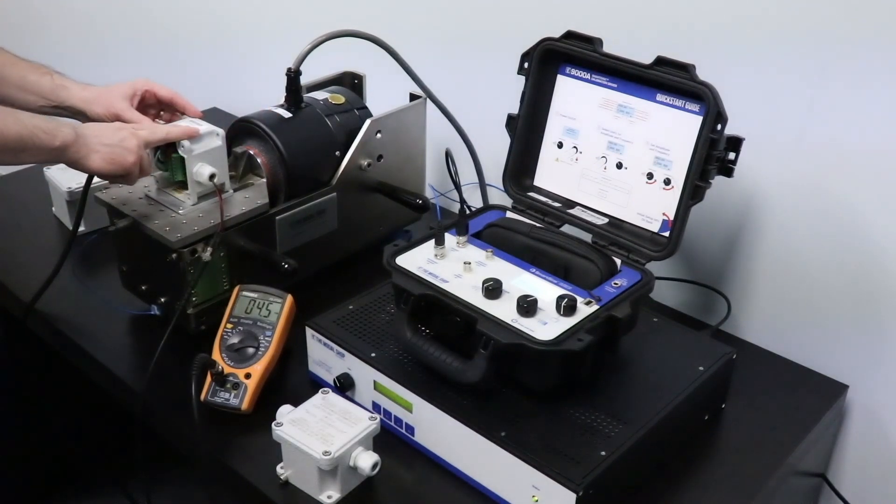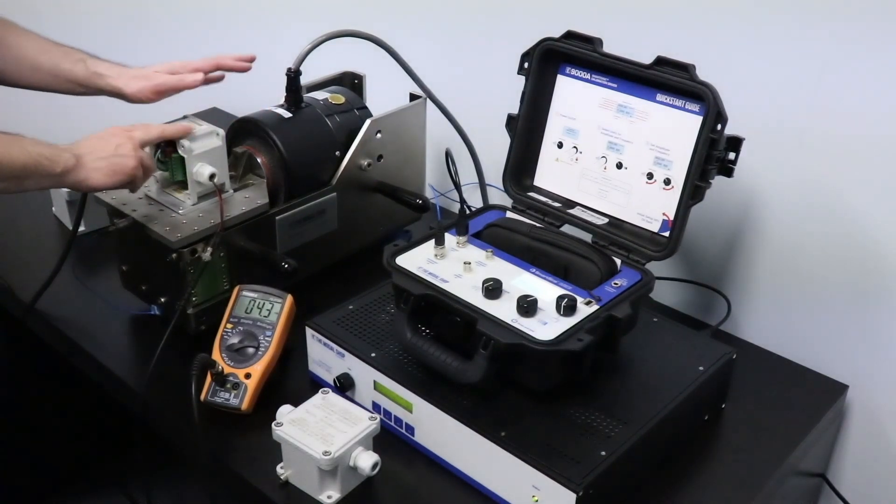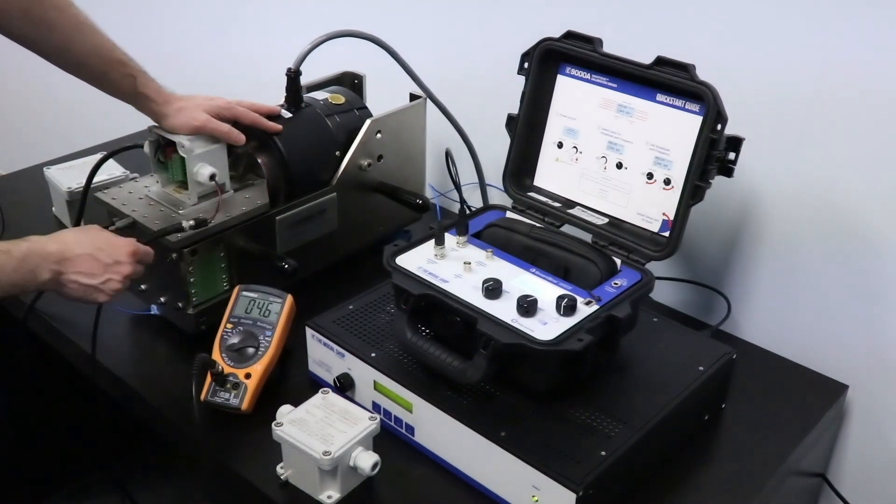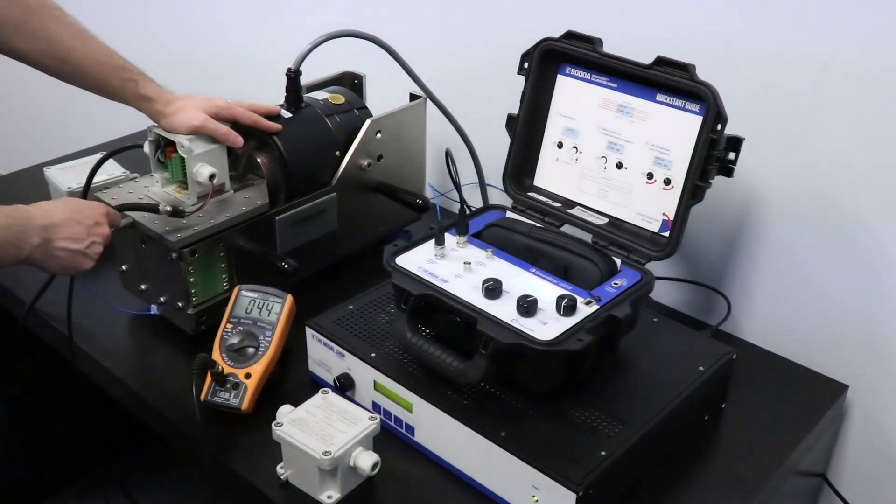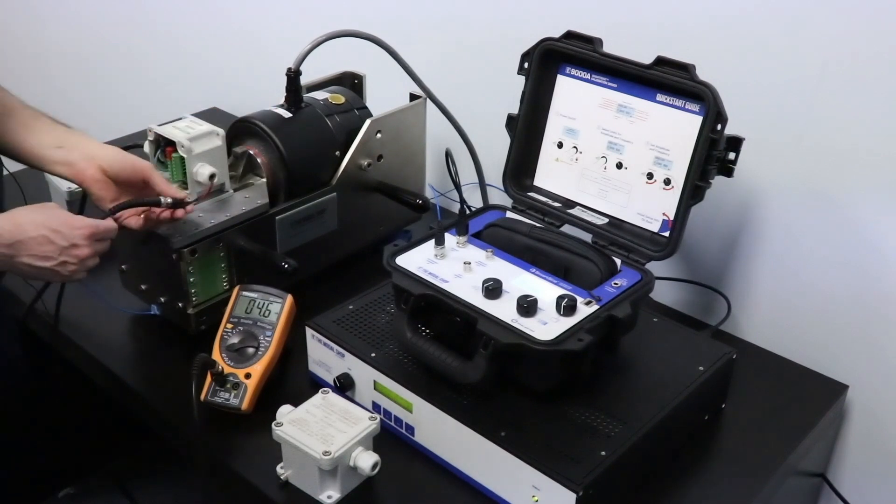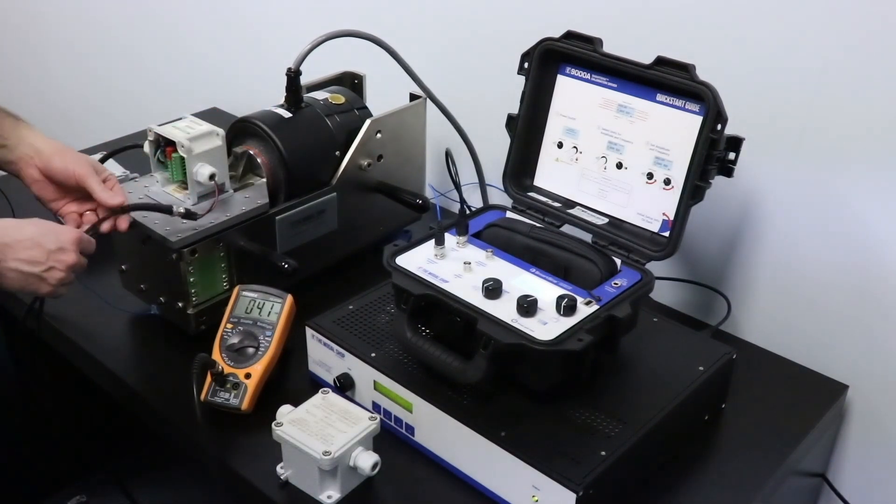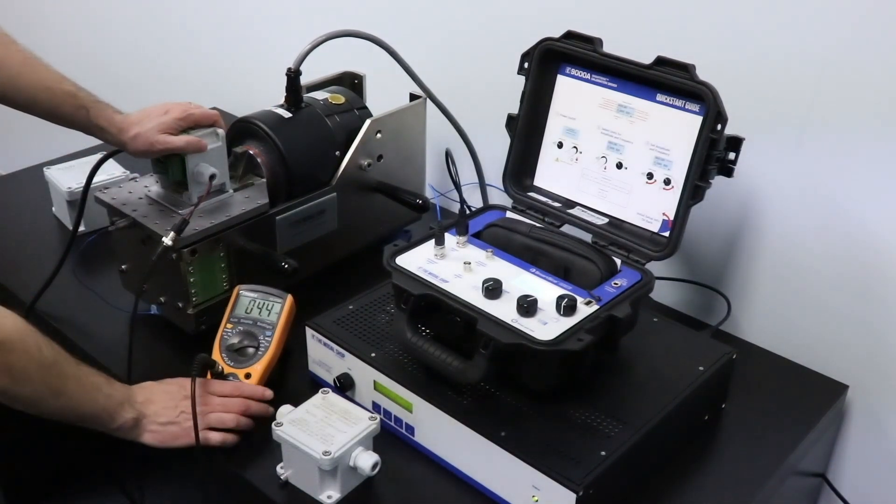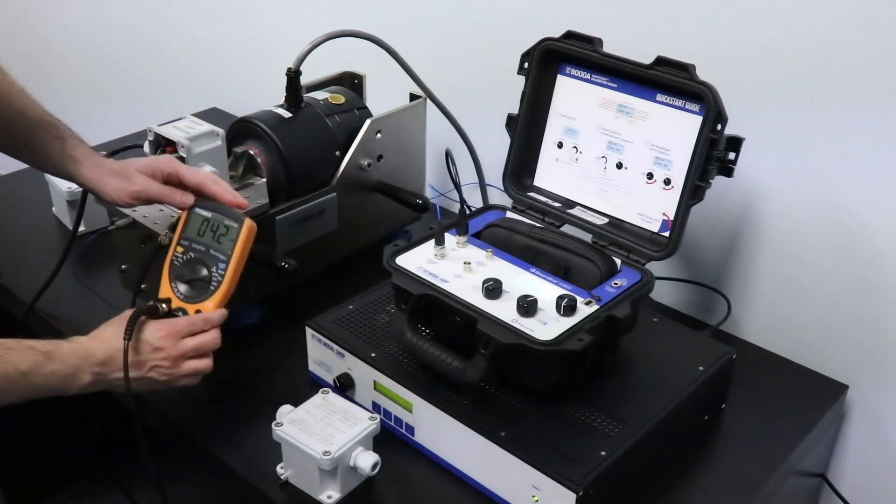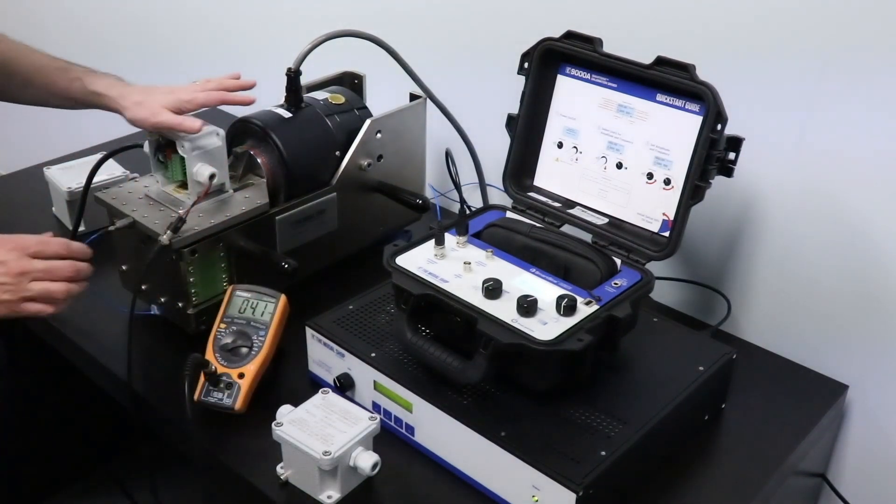So this particular switch is normally connected to a PLC or a DCS. And I have a current output coming out of it. So I'm monitoring that using this little current meter. I'm reading four milliamps right now, which means there's no vibration.